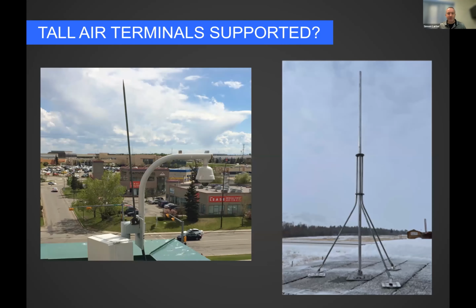Tall air terminals must be supported. Anytime you have a lightning rod over 2 feet, 600 millimeters, in height, you're required to support it at a point no less than half its height. On the left is a hospital here in Calgary with an old system. They wanted to protect a security camera, so they put up a really tall rod, but it has no support. That's technically not in compliance with code. Has it survived a good number of years? Yeah, it's doing its job, I guess, but it's still not in compliance.